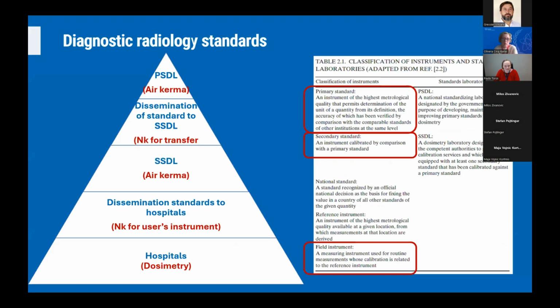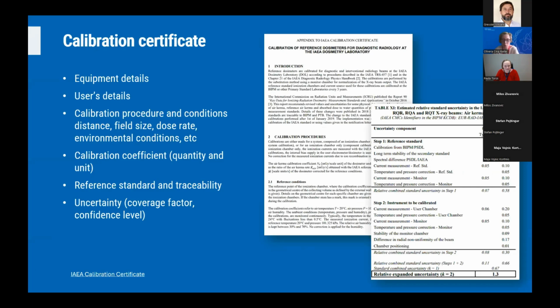Accuracy of dosimetry measurements is provided through the unbroken traceability chain, starting from the primary dosimetry laboratories to secondary laboratories to hospitals. And the main proof of the traceability and dosimetry accuracy is the calibration certificate. The calibration certificate is in fact a product of calibration, and by standard, mainly the ISO IEC 17025 standard, contains certain mandatory elements that are related to the equipment to be calibrated, user details, a short description of calibration procedures and conditions used during the calibration. The main product of the calibration is the calibration coefficient, and it should be presented in quantity and unit along with the associated uncertainty of calibration.